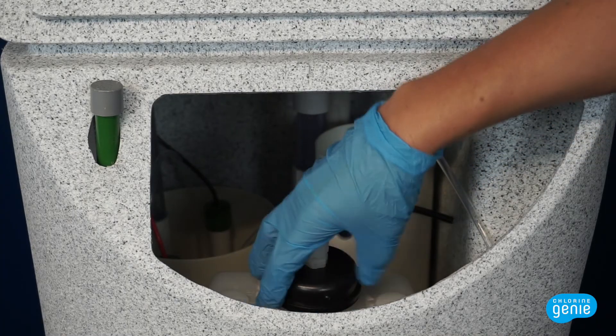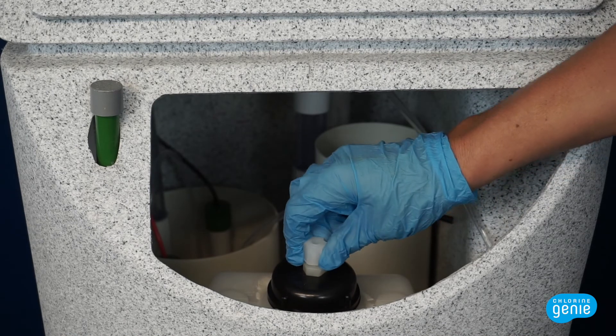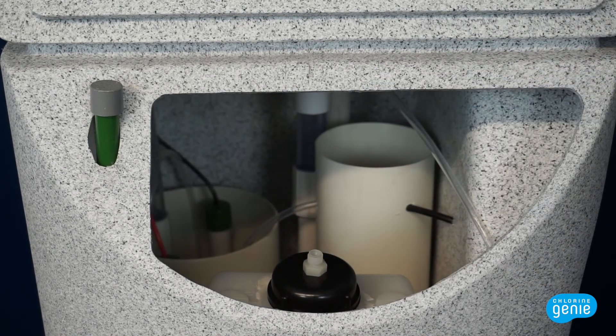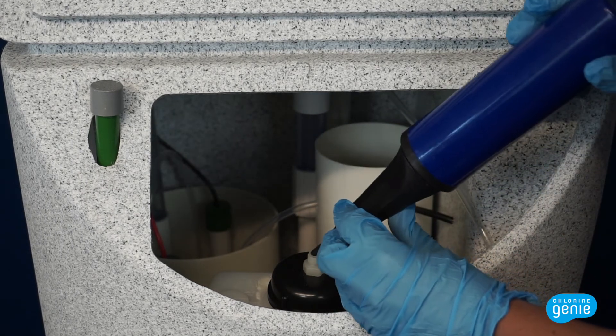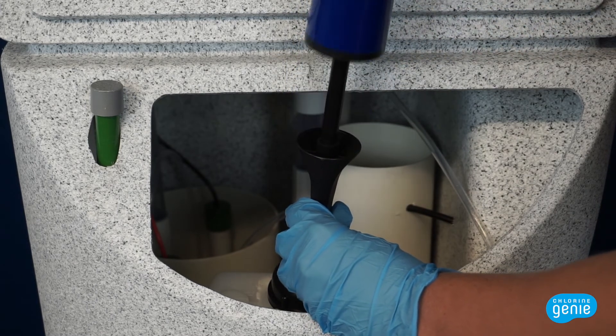With acid in the acid container, replace the cap and remove the nut on top of the cap. Put it somewhere safe so it does not fall into the tank. Take your air pump and insert the tip into the top of the acid tank and give it five pumps. You will see the muriatic acid moving through the lines inside the tank.